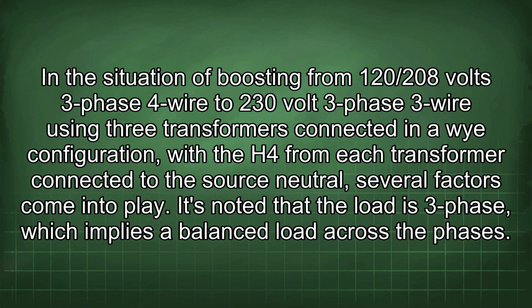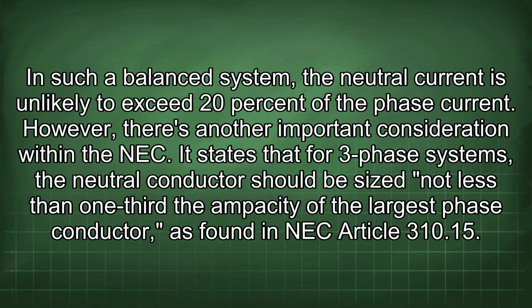In the situation of boosting from 120/208 volts 3-phase 4-wire to 230 volt 3-phase 3-wire using 3 transformers connected in a Y configuration, with the H4 from each transformer connected to the source neutral, several factors come into play. It's noted that the load is 3-phase, which implies a balanced load across the phases. In such a balanced system, the neutral current is unlikely to exceed 20% of the phase current.